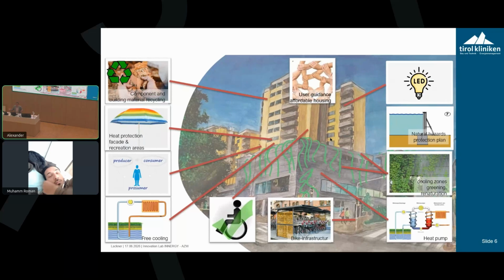For this, we have a bouquet of measures to come to our target. First of all, we want to change the lighting to LED. It's a very cheap and efficient way to reduce the power consumption. Afterwards, there was the point with the heating. Our hot water system was very inefficient. We have about 60 kilowatt heat load permanent, and this is a huge amount in summer. And we have at the neighbor ground a deep well. So there was the thought that we can use it for this area. So we have a cool water for cooling and also water for the heat pumps in the winter. This was the main idea.